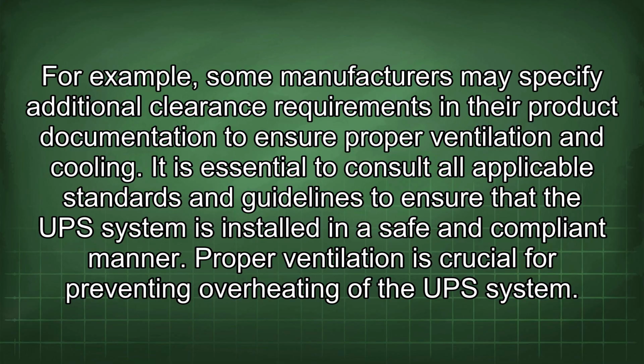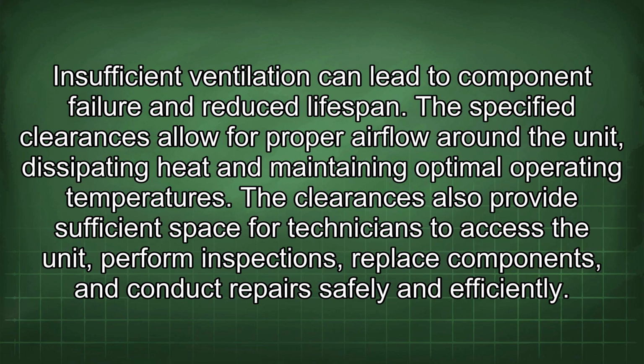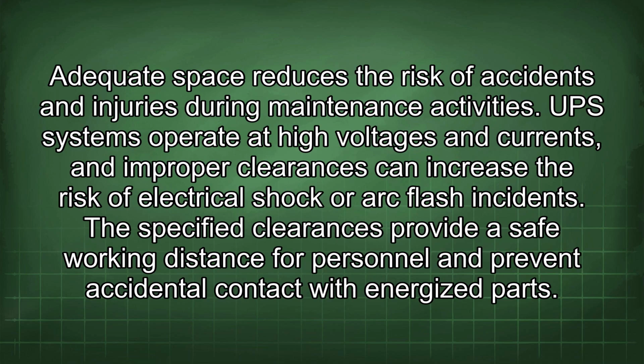Proper ventilation is crucial for preventing overheating of the UPS system. Insufficient ventilation can lead to component failure and reduced lifespan. The specified clearances allow for proper airflow around the unit, dissipating heat and maintaining optimal operating temperatures. The clearances also provide sufficient space for technicians to access the unit, perform inspections, replace components, and conduct repairs safely and efficiently. Adequate space reduces the risk of accidents and injuries during maintenance activities.